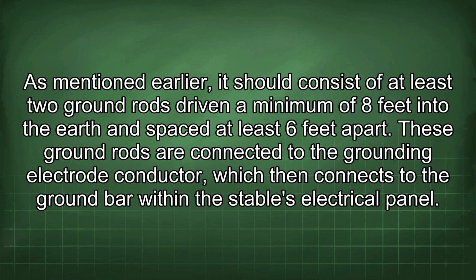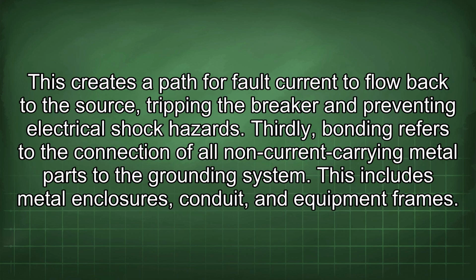As mentioned earlier, it should consist of at least 2 ground rods driven a minimum of 8 feet into the earth and spaced at least 6 feet apart. These ground rods are connected to the grounding electrode conductor, which then connects to the ground bar within the stable's electrical panel. This creates a path for fault current to flow back to the source, tripping the breaker and preventing electrical shock hazards.